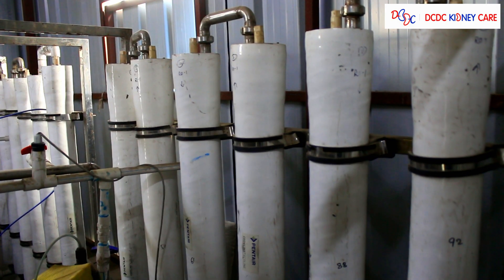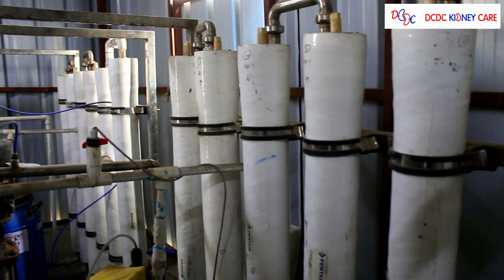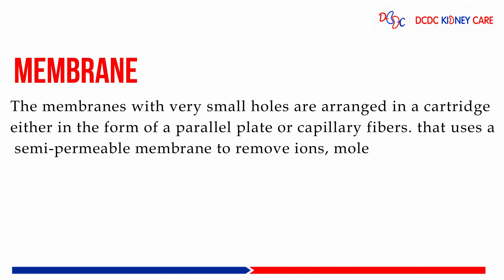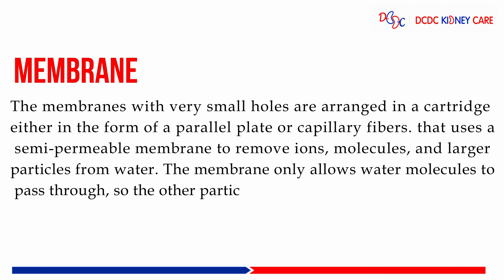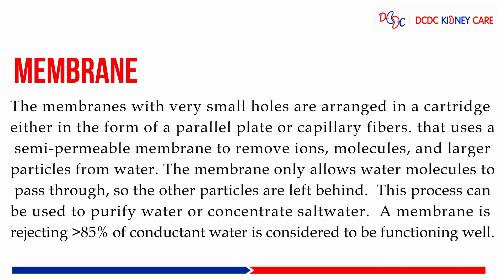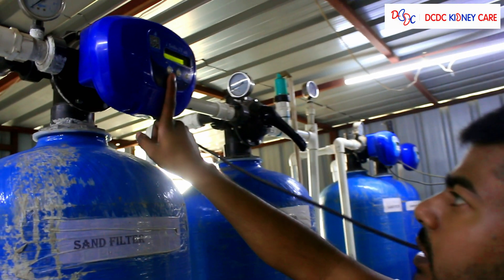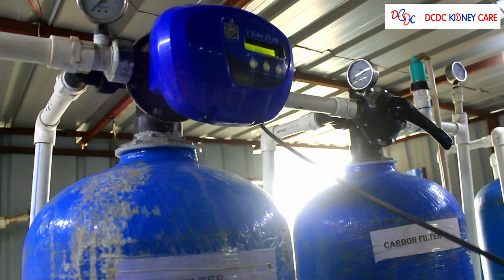Then the high pressure pump, which is used to send water to the membrane with high pressure. The membrane has very small holes and is arranged in a cartridge either in the form of a parallel plate or capillary fibers. It uses a semi-permeable membrane to remove ions, molecules, and large particles from water. The membrane only allows water molecules to pass through, so other particles are left behind. This process can be used to purify water or concentrate salt water.